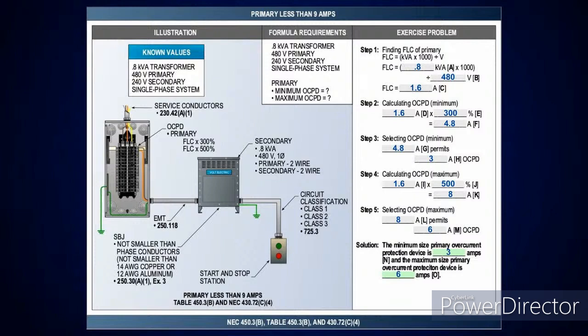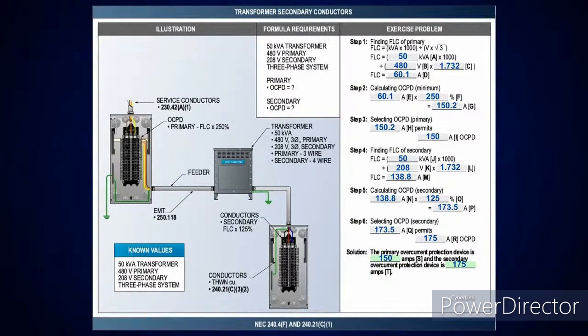Now, I can also go over and look at 430.72(C)(4), and it actually allows me to go up to 500%. So just take the 1.6 times 500%, which is 8 amps. Look over at table 240.6(A). The next size below that is a 6 amp. And that's for the primary only.